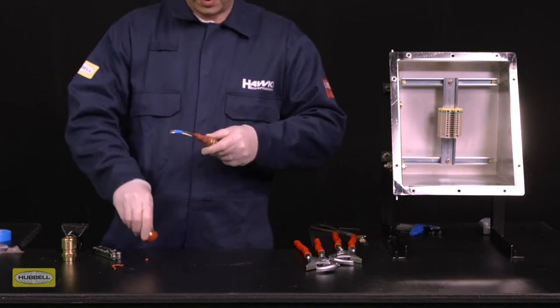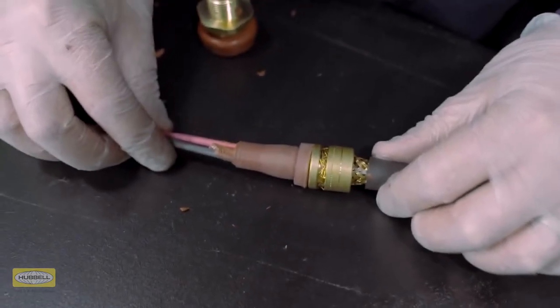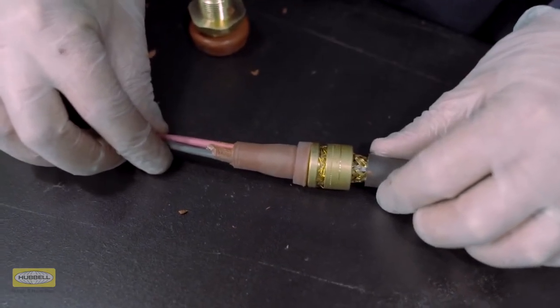Immediately remove the entry and inspect the compound for voids. This is the compound prior to installation in the entry. It has not been cured.